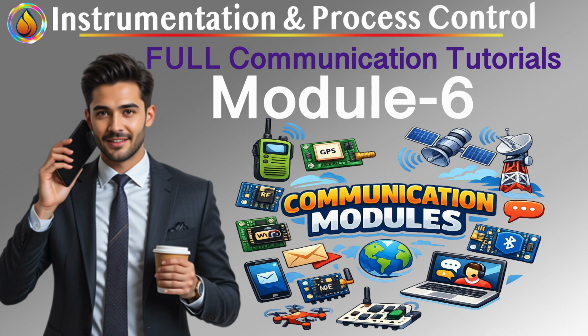Commissioning, from wiring to configuration. With Fieldbus, commissioning shifts from "Is this wire correct?" to "Is this device configured correctly?" That's a huge mental shift. You spend less time tracing cables and ringing out loops, and more time assigning addresses, mapping parameters, verifying communication. Commissioning becomes systematic, not manual.